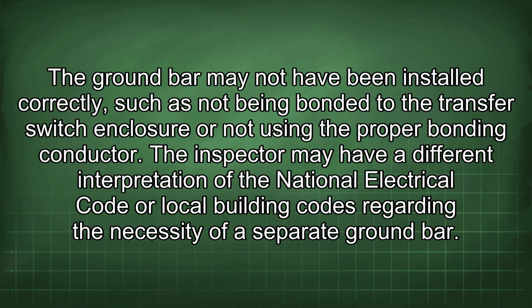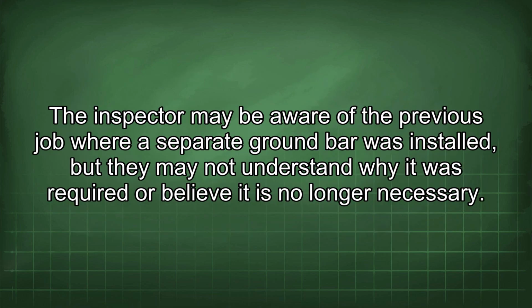The ground bar may not have been installed correctly, such as not being bonded to the transfer switch enclosure or not using the proper bonding conductor. The inspector may have a different interpretation of the National Electrical Code or local building codes regarding the necessity of a separate ground bar. The inspector may be aware of the previous job where a separate ground bar was installed, but they may not understand why it was required or believe it is no longer necessary.